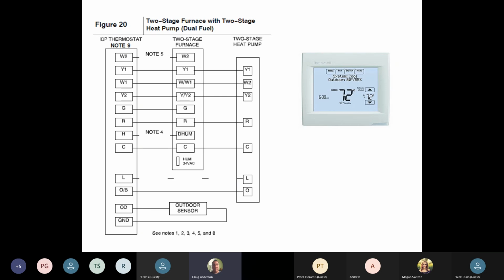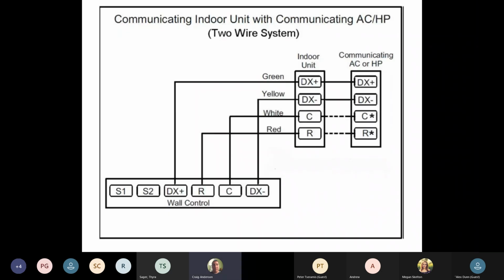Wi-Fi is not going to allow it to run because it's telling you it's -25 outside. This is telling you what the temperature is of that heat pump at that time of the day where it is sitting, so you can get some more run time. If your Wi-Fi is out, you're not reading outdoor temperature. If you're getting glitches, you're not getting outdoor temperature. So just things to look at when you're working on this. We can do a Honeywell Stat Wi-Fi and still put an outdoor sensor on it, wired. Go that route, your customer will probably be happier.